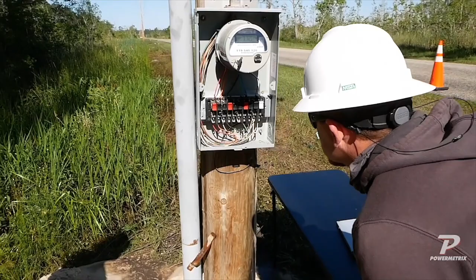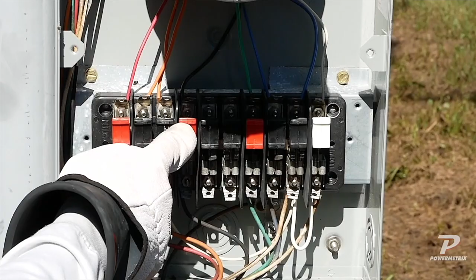I'm seeing 3 voltages, 2 currents. I know it's a 5S, so we're probably looking at a 4-wire delta. Jonathan points out that B phase is always the one you check to see what's going on. Looking there, no currents on the B phase switches, but we do have a B phase voltage, so that confirms 3 voltages and 2 currents. Notice how he looked at it: no currents, but a voltage on B phase, because that phase always tells you whether it's grounded or open on a 5S. We're connected on the voltage but not the currents, so overall 3 voltages and 2 currents.